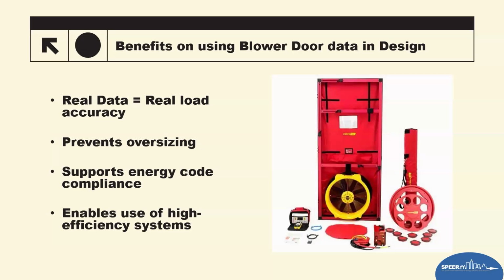So it can prevent over and undersizing, and oversizing is the worst option. It supports energy code compliance, because it's been a requirement in code for several cycles. There are still areas of Texas, and of course across the country, that don't require blower door testing or don't require duct testing. So there's no validation happening. Even though something is projected or assumed, it's never verified as a reality.